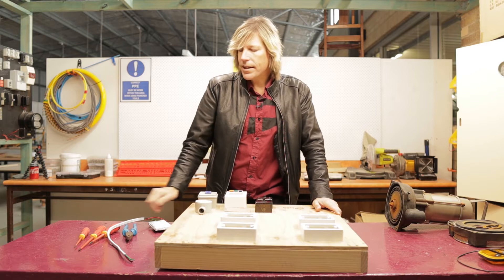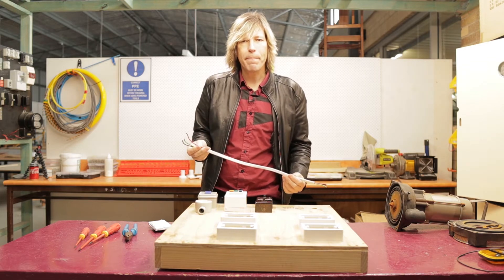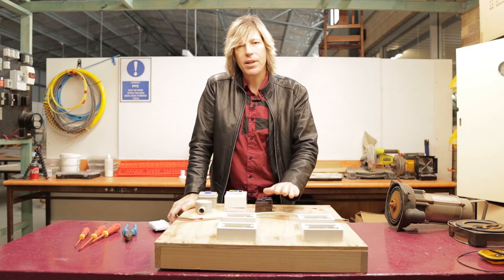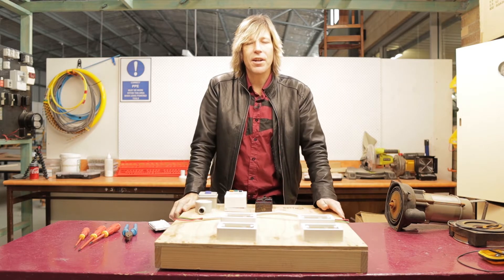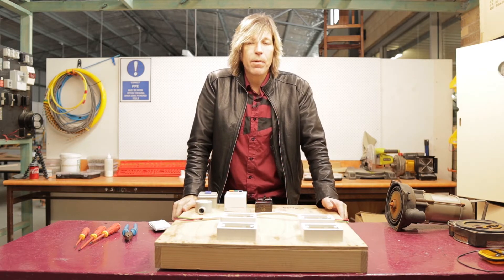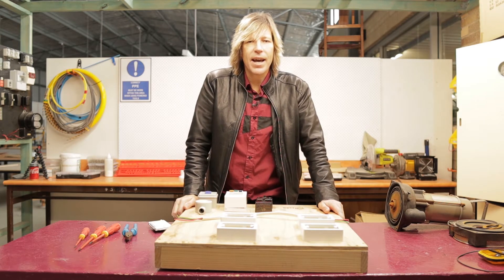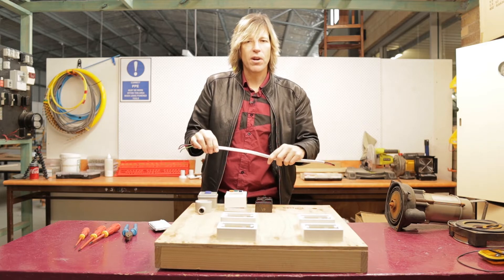The first thing we are going to need is some cable. This is TPS cable. It is 2.5mm cross-sectional area, and that is rated up to about 20 plus amps. We can check the ratings of our cables in the AS/NZS 3008, and that will give us an idea of what cabling we should be using. Generally, you are looking at running a 2.5mm cable for GPO circuits, because GPO circuits are rated at about 16 amps. So this cable will comfortably carry 16 amps regardless of where it is being put.